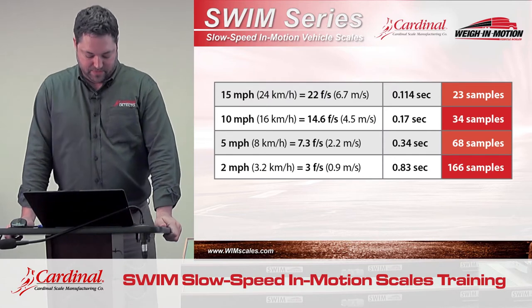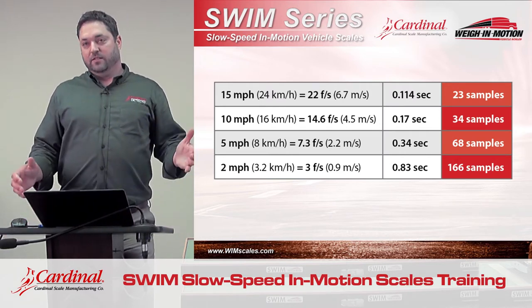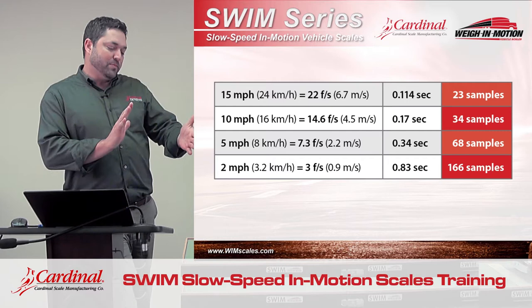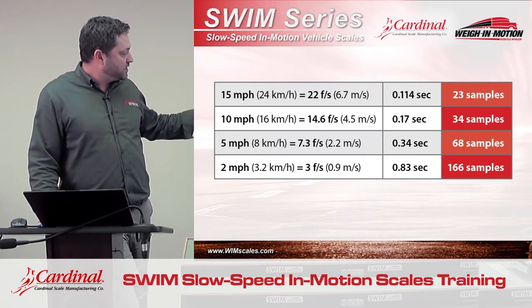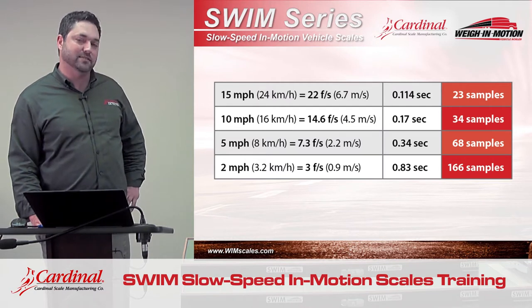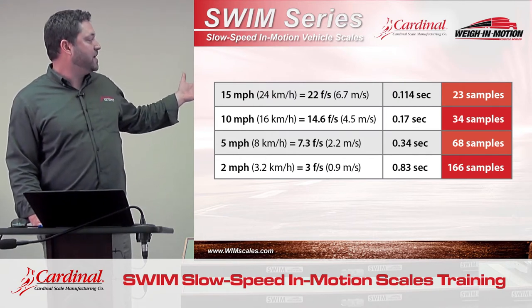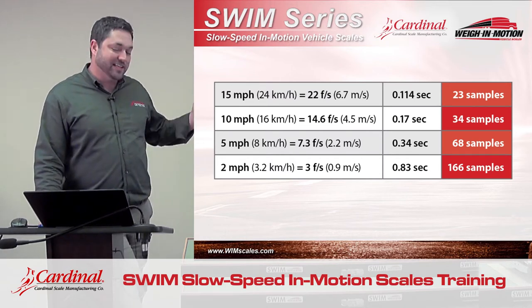Inside the 825, the dynamic software is sampling the load cells at a rate of 200 samples per second. So for any one second that the tire is on the weigh bridge, you'll get 200 samples in order to calculate a weight. Because the weigh bridge is only 30 inches across, at two miles an hour the vehicle is traveling at three feet per second, which means that axle is only applying force to the bridge for about 0.8 seconds — during which we can capture 166 samples. That's a good amount of samples to calculate the dynamic weight. At 15 miles per hour, the vehicle is traveling at 22 feet per second, and that axle is only applying weight to the weigh bridge for about a tenth of a second, giving us just 23 samples.